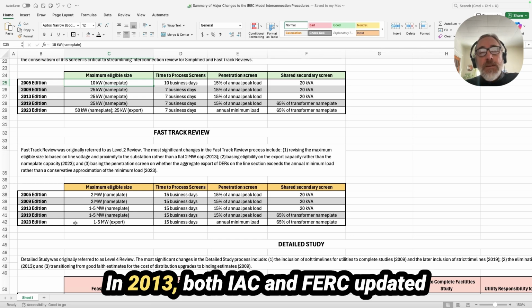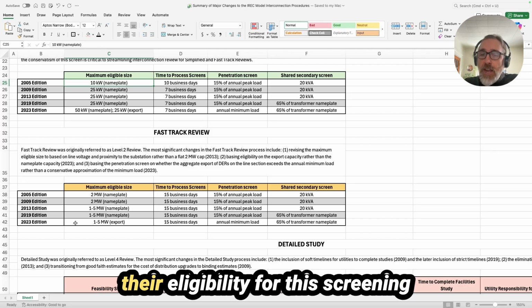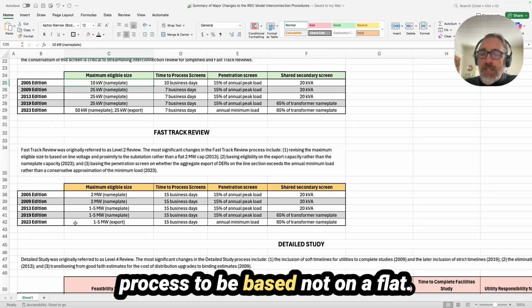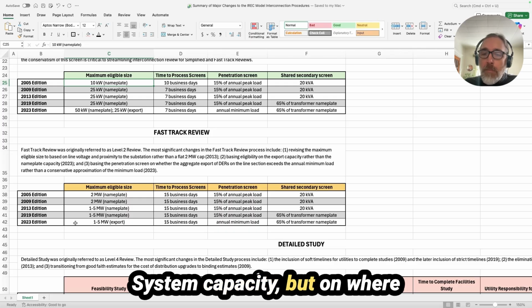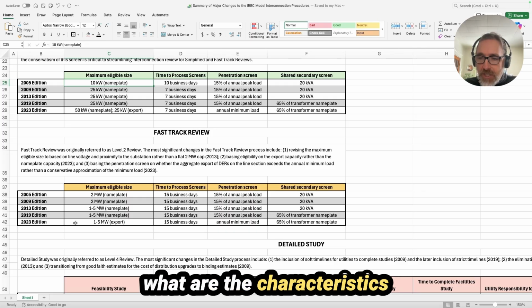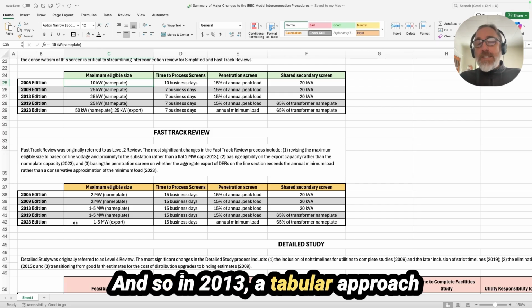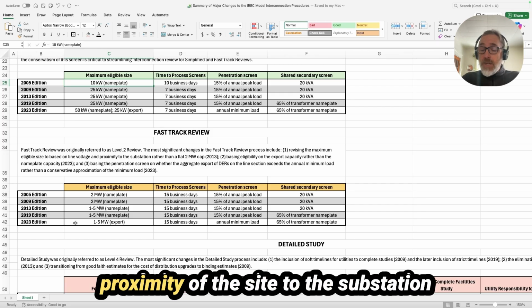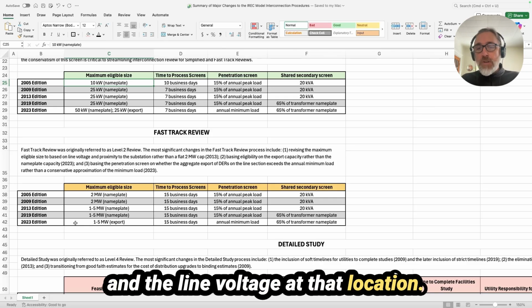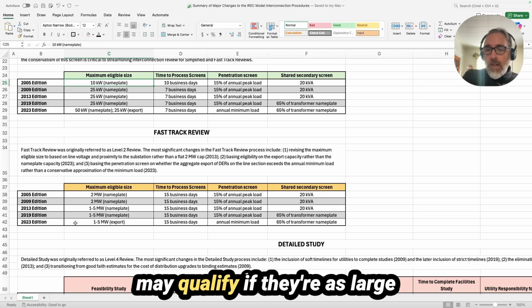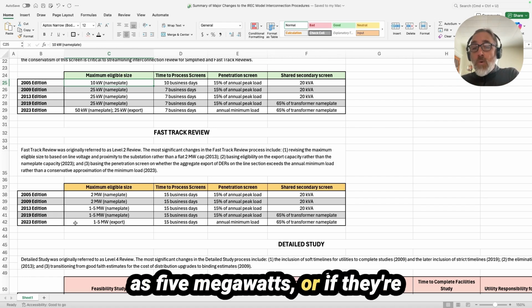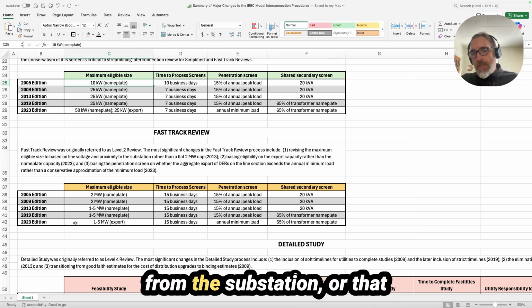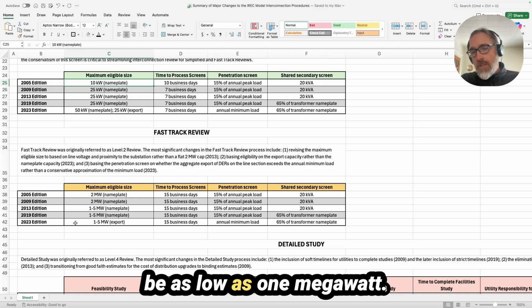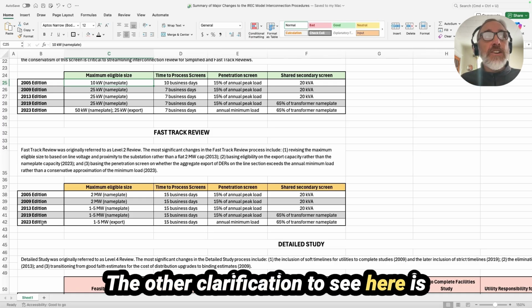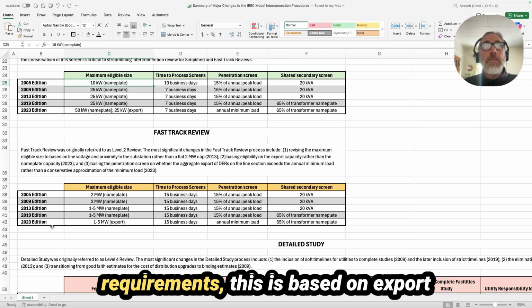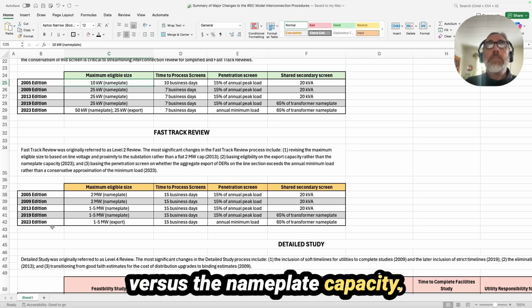In 2013, both IREC and FERC updated their eligibility for this screening process to be based not on a flat system capacity, but on where it's located on the grid and what are the characteristics of the grid in that location. And so in 2013, a tabular approach was introduced based on the proximity of the site to the substation and the line voltage at that location. And this means that projects may qualify if they're as large as 5 megawatts, or if they're on low voltage and far away from the substation, or that information's not known, it may be as low as 1 megawatt. The other clarification to see here is in 2023, like a lot of other eligibility requirements, this is based on export versus the nameplate capacity.